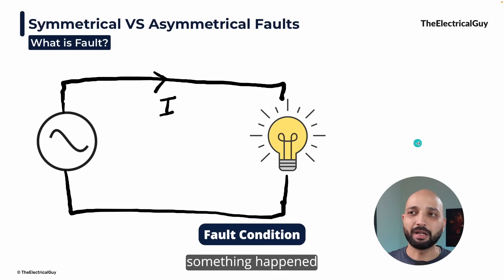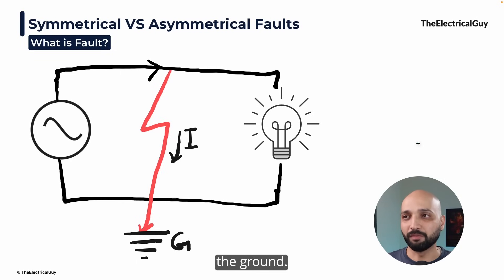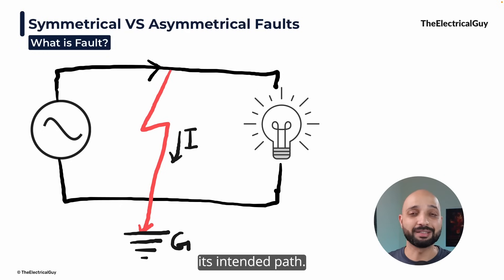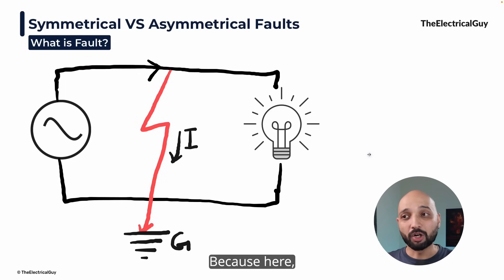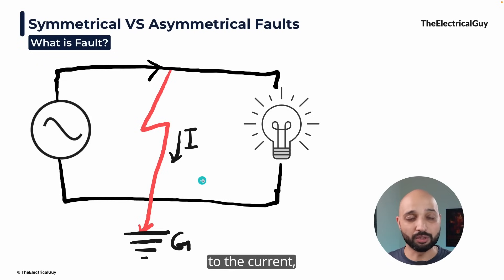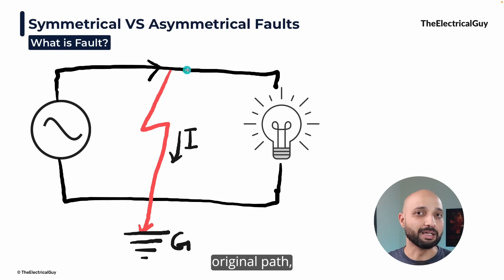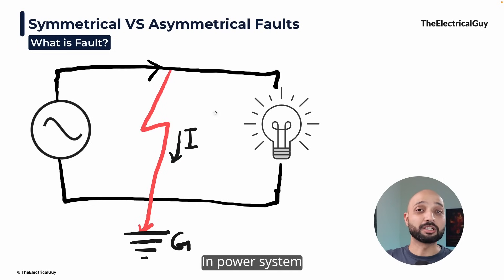For example, let's say something happened and one of the phase wires is now touching the ground. As a result, this connection is created and the current will start flowing through this path and not from its intended path. Why? Because this newly created path is offering less opposition to the current — less impedance. And since the impedance offered by this path is much lower than the original path, the amount of current that flows through this will be very, very high. In power systems, it can go to several thousand amperes.